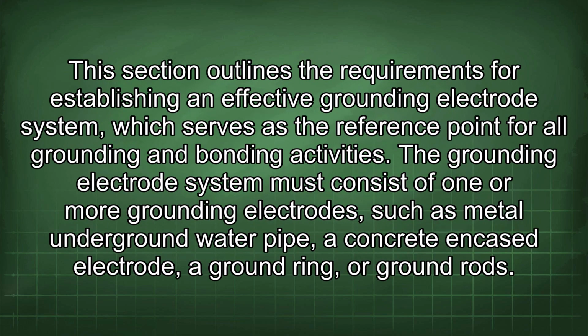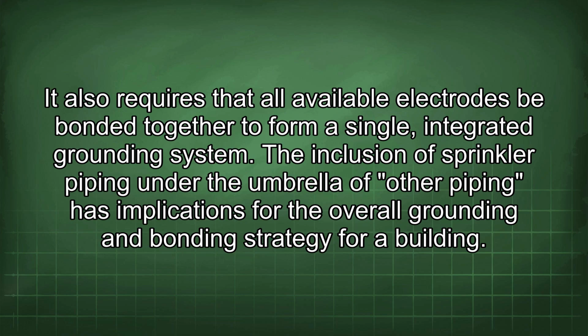This section outlines the requirements for establishing an effective grounding electrode system, which serves as the reference point for all grounding and bonding activities. The grounding electrode system must consist of one or more grounding electrodes, such as metal underground water pipe, a concrete encased electrode, a ground ring, or ground rods. It also requires that all available electrodes be bonded together to form a single, integrated grounding system.